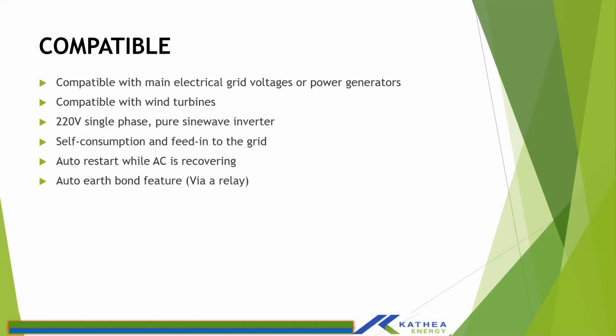And so when the inverter is operating in island mode, that is in off-grid mode, when you don't have grid connected to it, you would need to have your neutral and earth bonded together, right? So if, let's say, the premise's earth and neutral are not bonded together, the inverter offers an auto earth bonding feature, which is a relay. It has an output of 220 volts, so you'd need to wire through a relay such that when the system loses grid, this output is energized, and then it will energize your relay to bond together your earth and neutral.